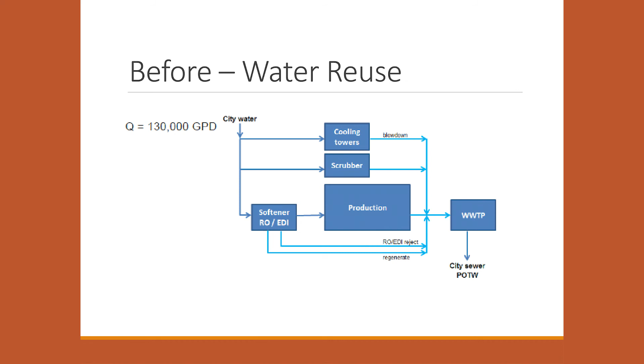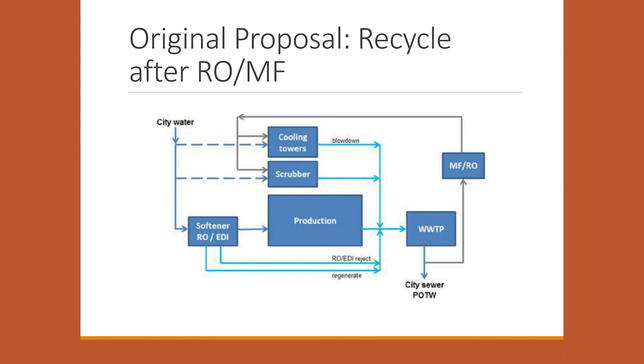So at first they were thinking they needed to put in this membrane facility, do some reverse osmosis to be able to reuse that water because they had to remove all the salts. But then they went through the 5 whys of asking, why is this water so hard? And they realized that the cooling tower blowdown and the softener regenerate were really the 2 only really hard water processes coming through this plant. So instead of building the membrane facility, they just sent the blowdown and the regenerate out of the system, and they took the rest of the water, put it through the on-site wastewater treatment plant, and that was enough purification for them to reuse that water again.